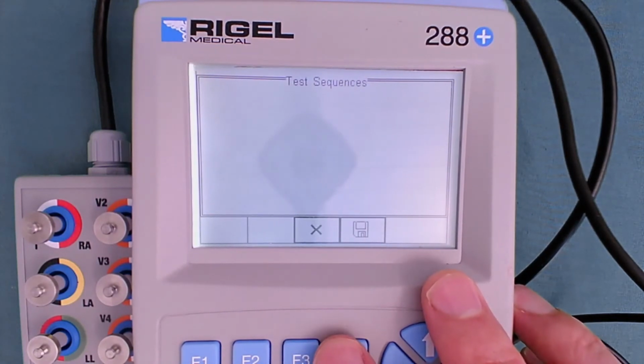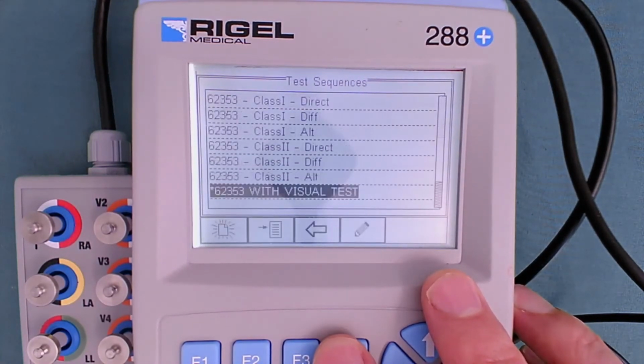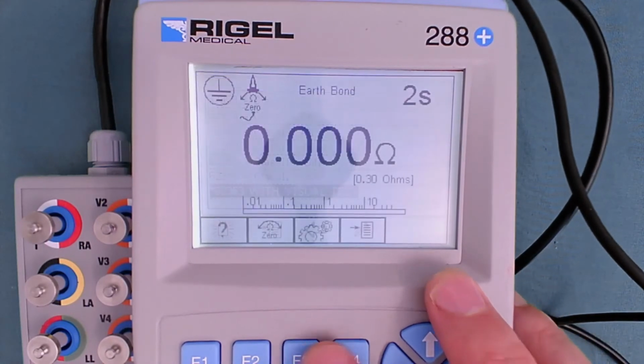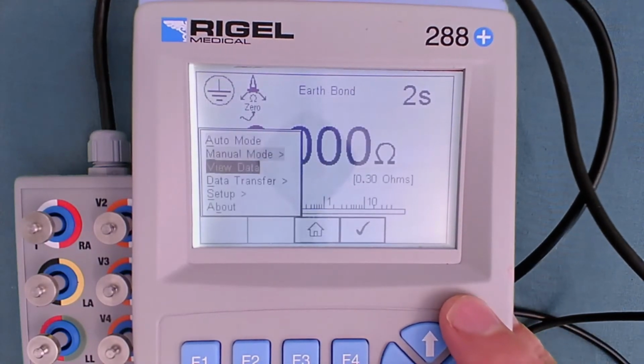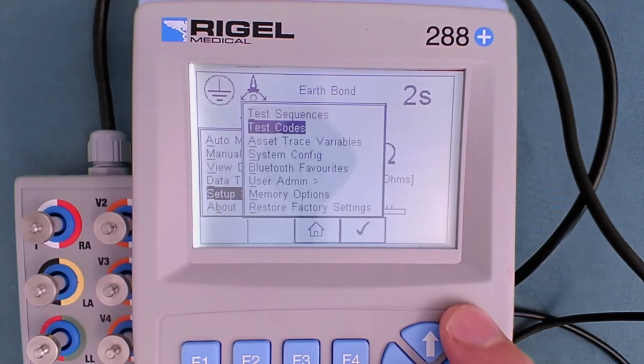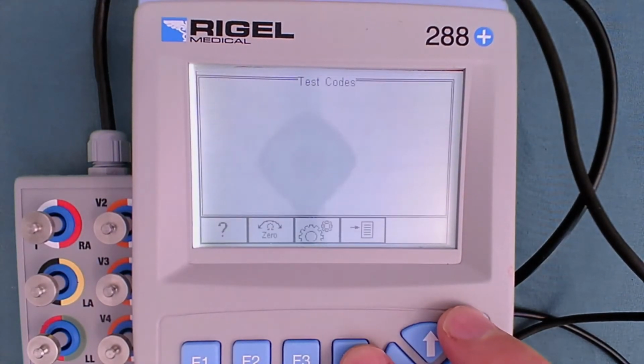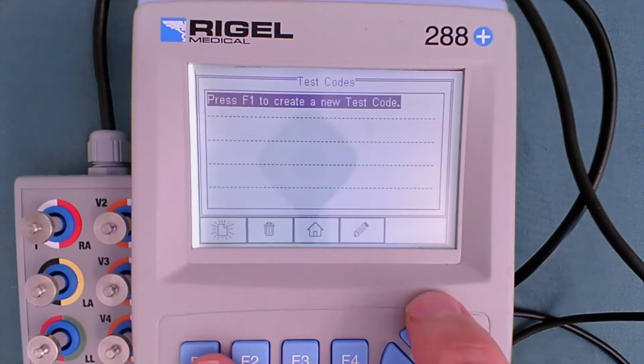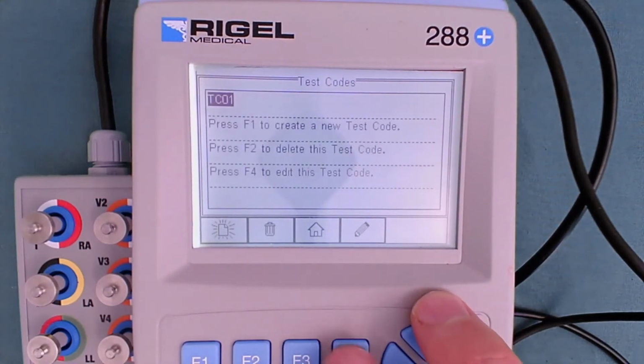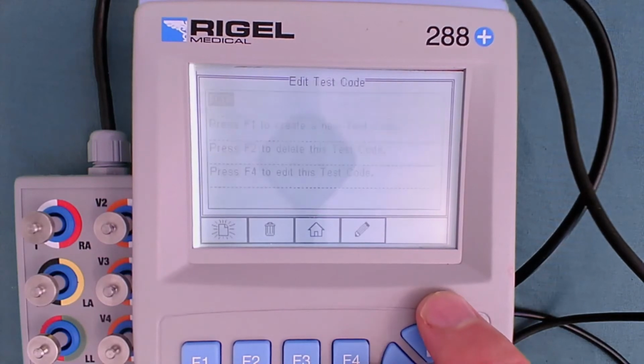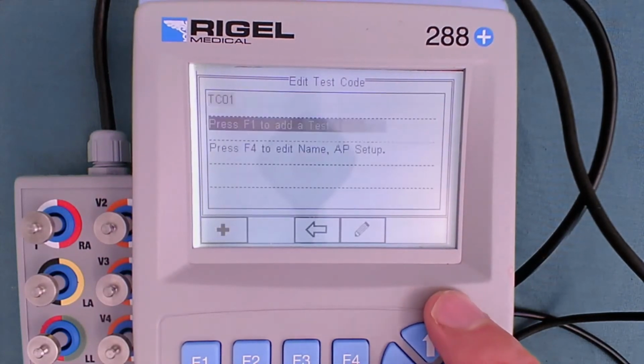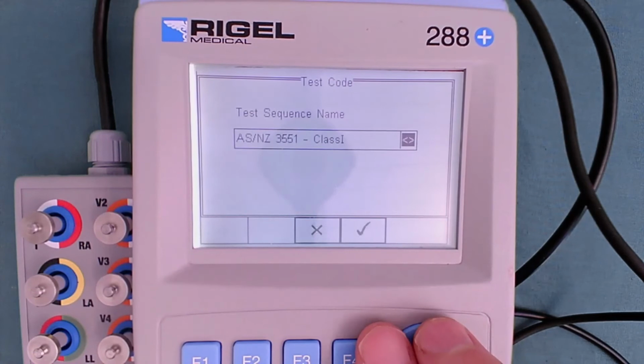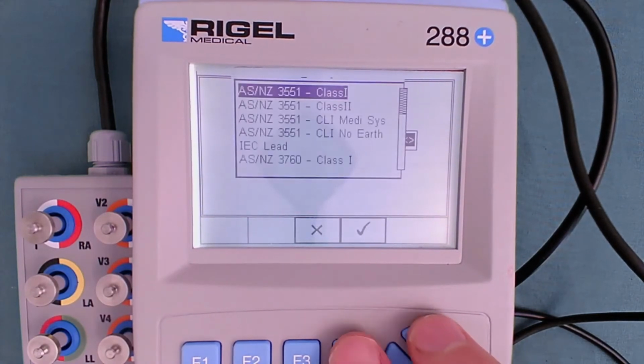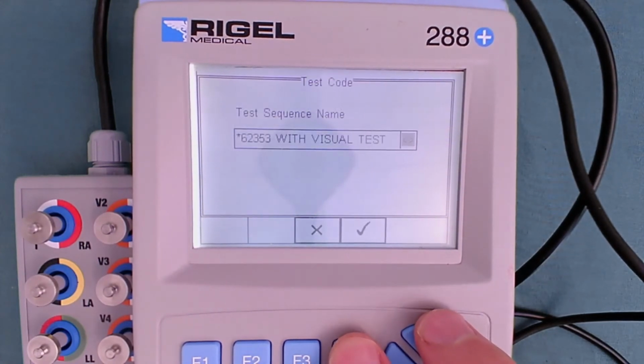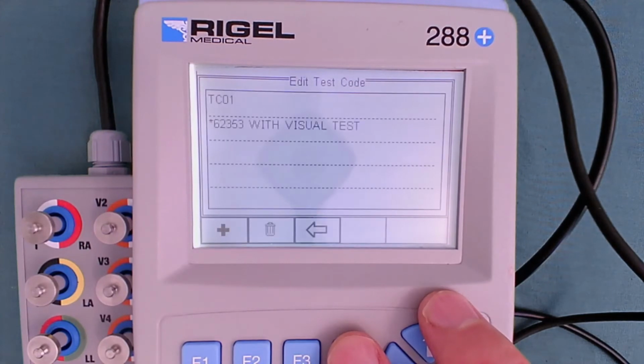It'll be part of your automatic mode test procedure if you require it. One thing I didn't show on the presentation is test codes, and these are really useful if you've got different configurations of applied parts. So let's create a test code using that same test sequence. This one, when you create it, called TC01. Add our test sequence. So in this example, we're going to use the one we've just created, 62353 with visual test. Select F4, F3 to go back, and that's now saved.